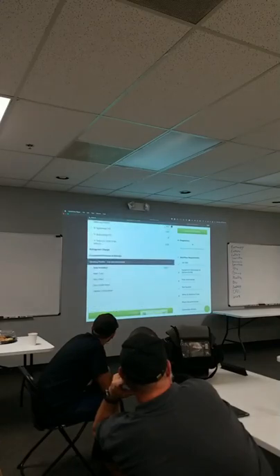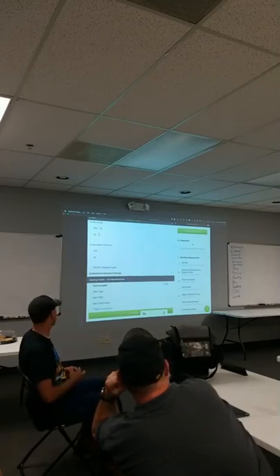And most commercial stuff is not rated by SEER. A pretty safe bet is 10 to 12 SEER for a lot of the older stuff, closer to 13 SEER for the current stuff. If there's a different target subcooling setting in here, like maybe 9 degrees, we put that in. If we know the amount of refrigerant that goes in that system, we can put that in pounds and ounces. So we can, let's say, 12 pounds and 3 ounces. That actually works for a charge assist that we have on this.